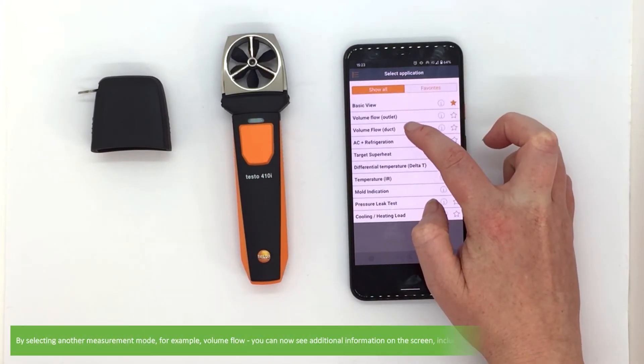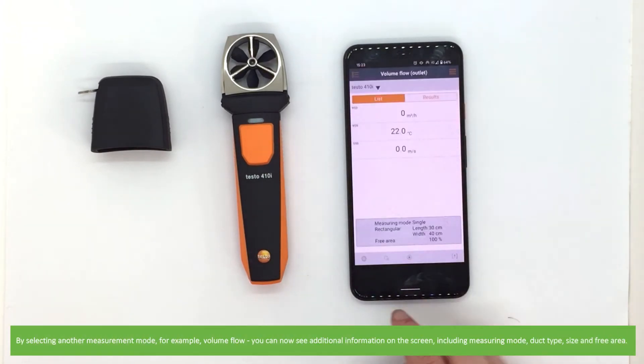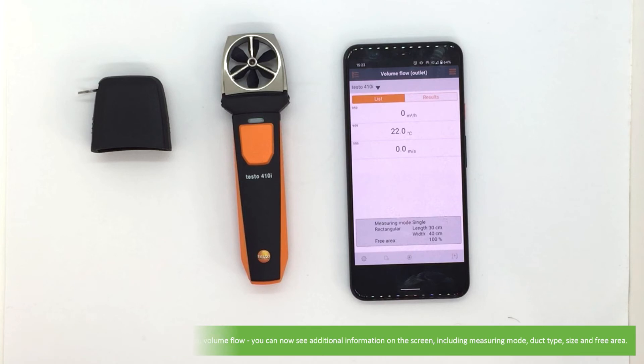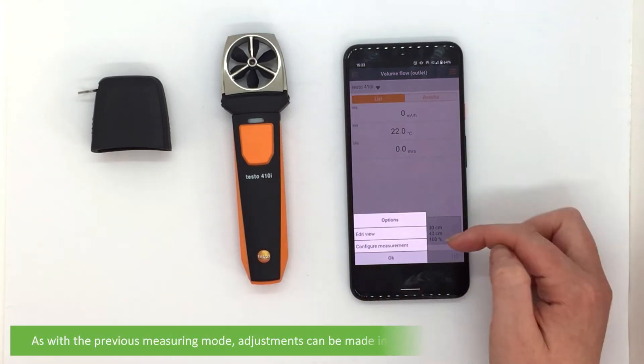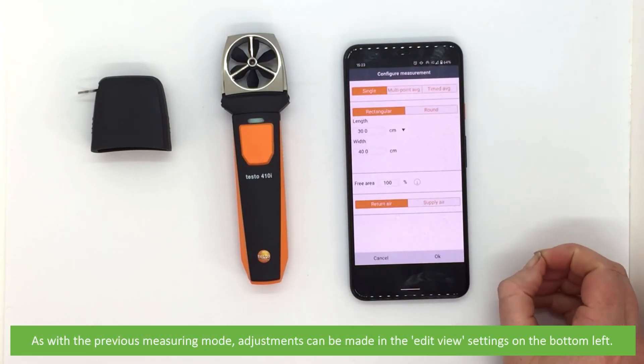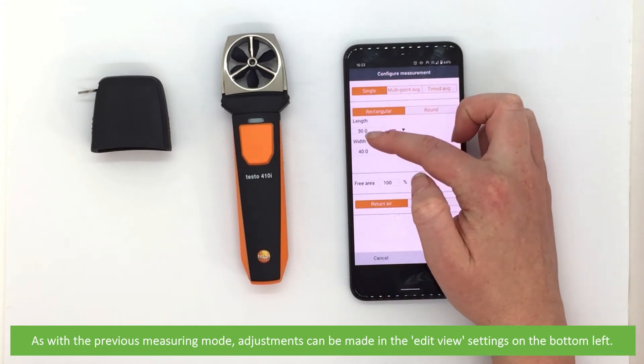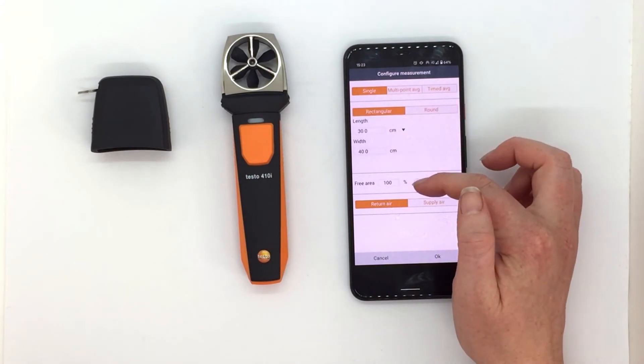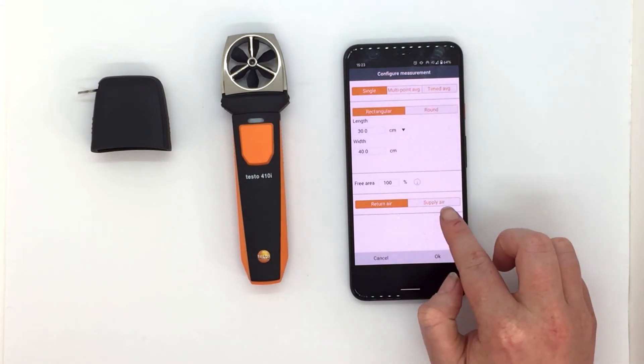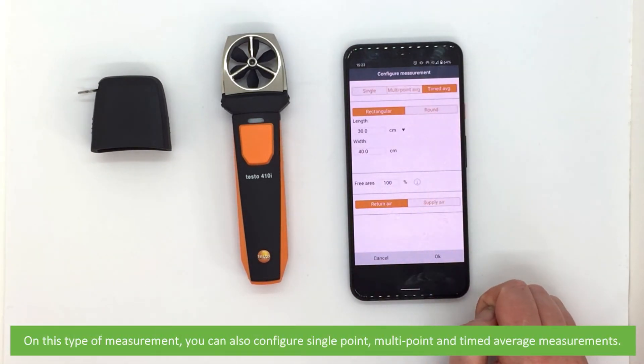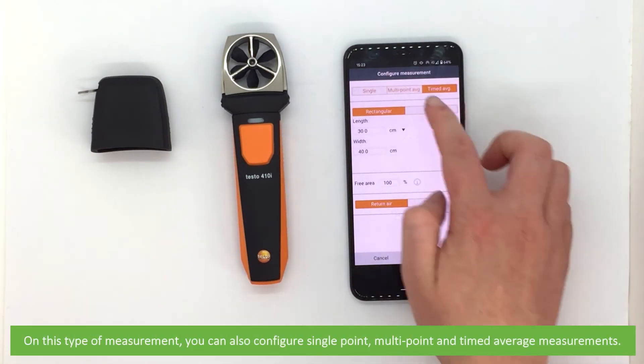By selecting another measurement mode — for example volume flow — you can now see additional information on the screen including measuring mode, duct type, size and free area. As with the previous measurement mode, adjustments can be made in the edit view settings on the bottom left. On this type of measurement you can also configure single point, multi point and timed average measurements.